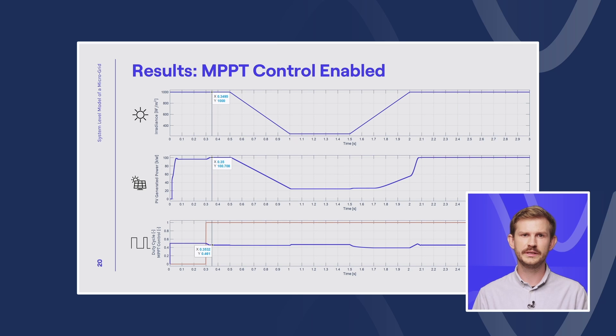But once we enable our MPPT control, we can experience the control of the duty cycle, and we can see that we are able to raise the output power of the PV array to 100.7 kW. This is more than a 4% of gain, which is significant if we consider the fact that we are able to reach this only with an efficient control of our boost converter.